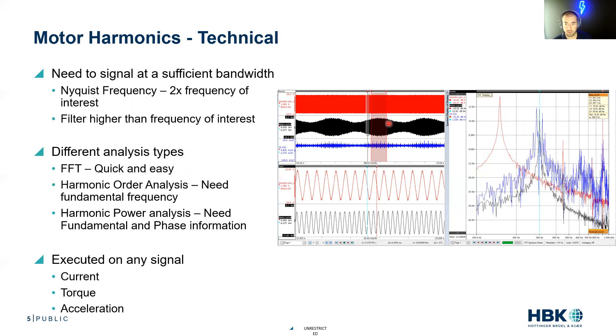We can see my torque ripple and my accelerometer have some content as well. I show this because we can do these types of analyses on any signal - on current, on torque, on acceleration. We can do all these analysis types on all these different signals. We can do an FFT, which is that fast Fourier transform, which is just a quick snapshot. We can do harmonic order analysis where we need to know the fundamental frequency. And we can do harmonic power analysis where we can actually look at the power content of each harmonic.